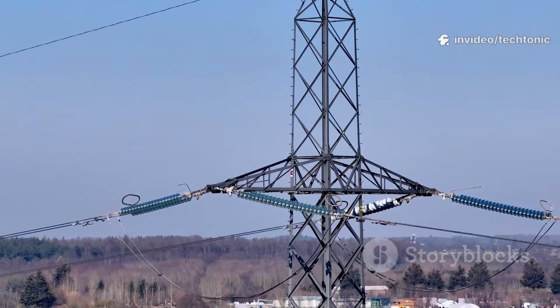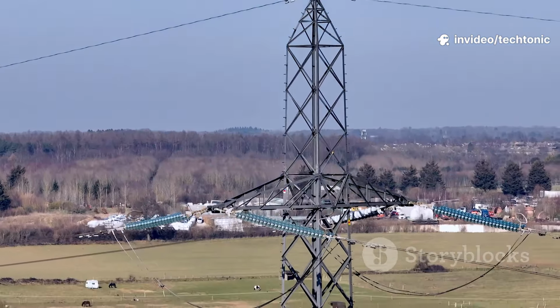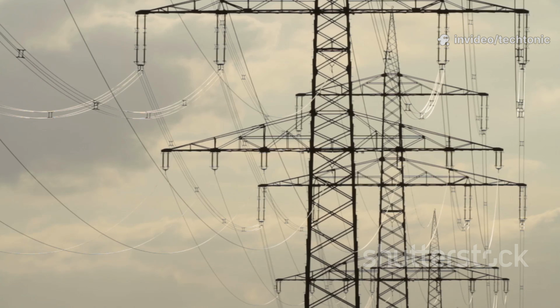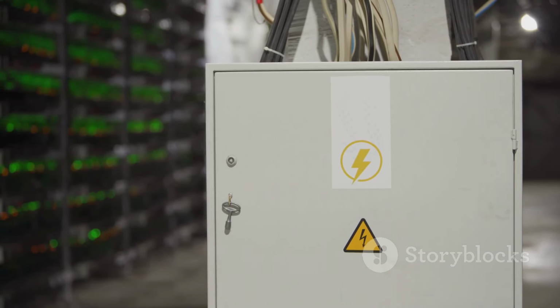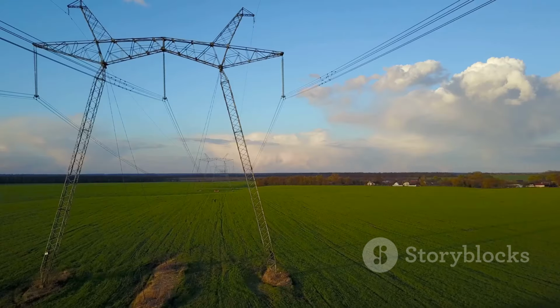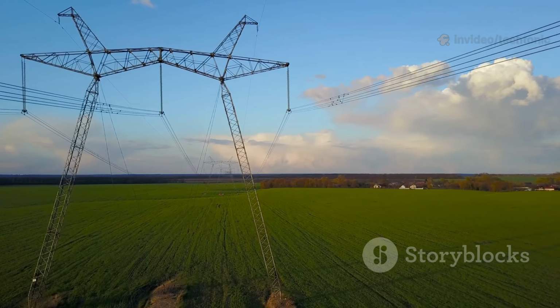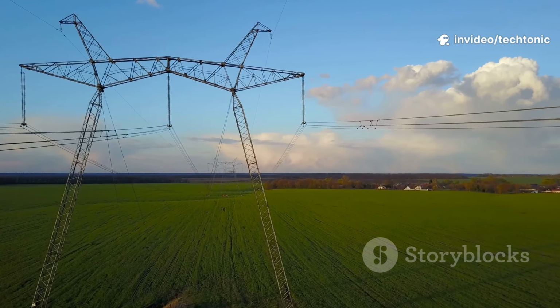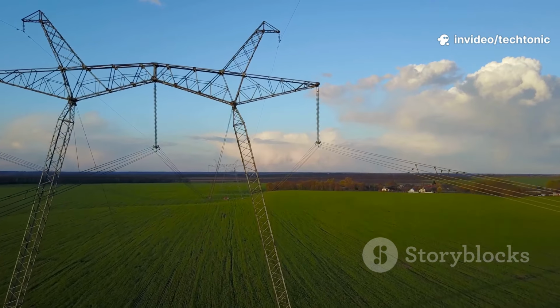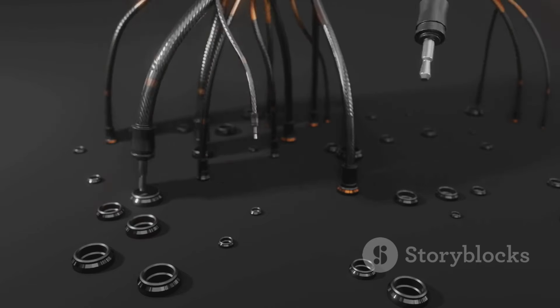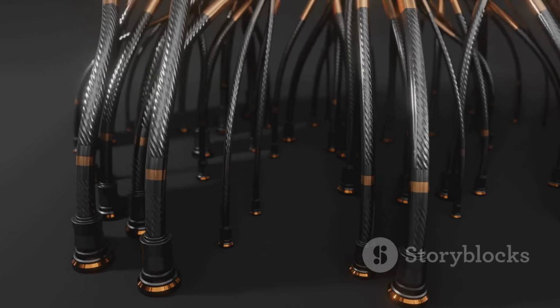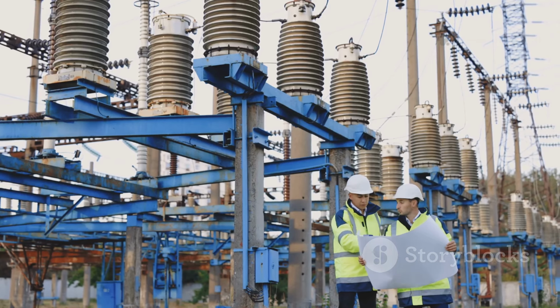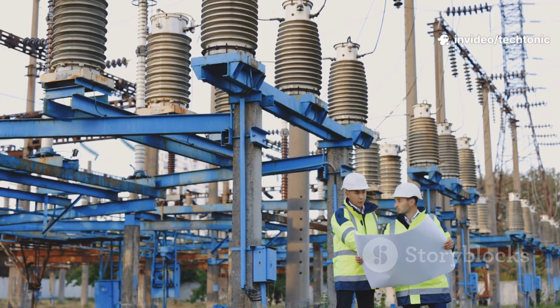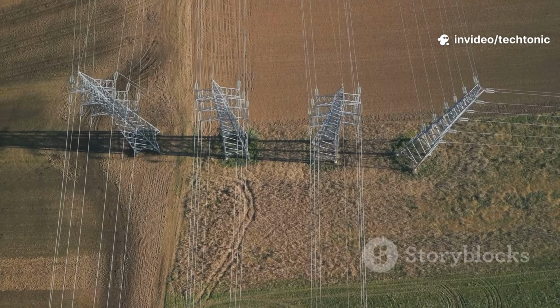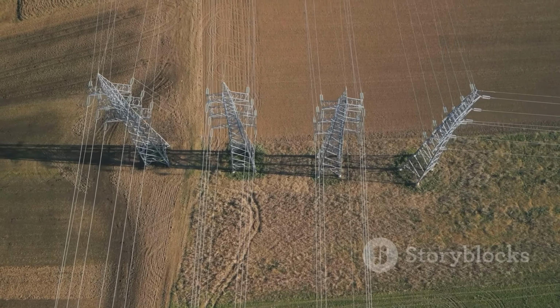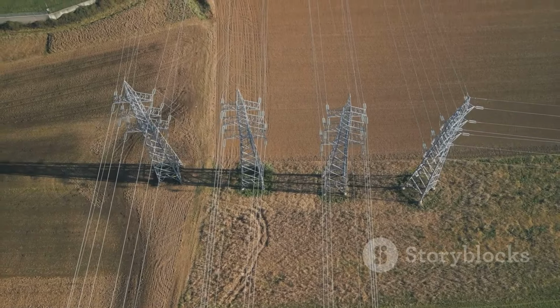So, how does HVDC magically avoid all these problems? It's all because direct current is steady and straightforward. With DC, the voltage is constant, and the current flows in only one direction. This means it creates a static magnetic field and a stable electric field. So, there's no inductive or capacitive interference with the surroundings. Furthermore, because the frequency is zero, the skin effect completely disappears. The current flows uniformly through the entire cross-section of the conductor, making the most efficient use of the material. It's a much calmer, more orderly way to move electrons, which results in lower power losses over long distances.